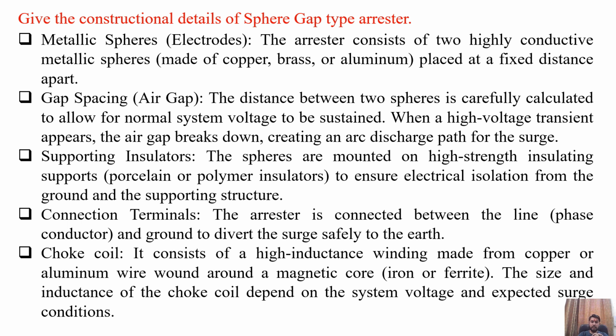Supporting insulators. The spheres are mounted on high strength insulating supports made up of porcelain or polymer material, or insulators, to ensure electrical isolation from the ground and the supporting structure. Connection terminals. The arrestor is connected between the line, that is the phase conductor, and ground to divert surge safely from line to earth. Choke coil.